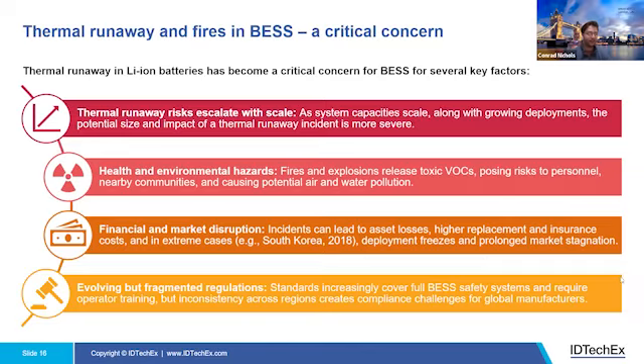As BESS capacities scale and deployments grow, there is an increased risk of thermal runaway and potential for a larger scale event like a fire or explosion, and therefore stricter BESS safety measures are required. But beyond fire and explosion damage risk and risk to personnel, toxic gases can be released as a byproduct of the battery electrolyte decomposing—things like hydrogen fluoride and hydrogen gas itself. These gases can pollute waterways and the environment, harming wildlife and populations.